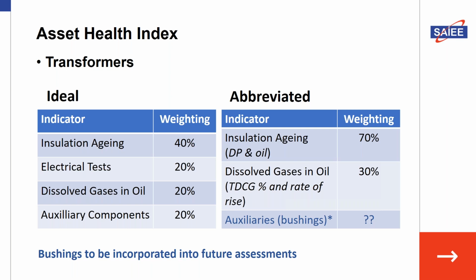If you look at insulation aging of the transformer, you weight it at 40%, then conduct a whole series of electrical tests. One popular one is called SFRA, a digital footprint of how the windings react to impulses - it's a proxy indicating the winding hasn't changed over time if that digital signature remains constant.